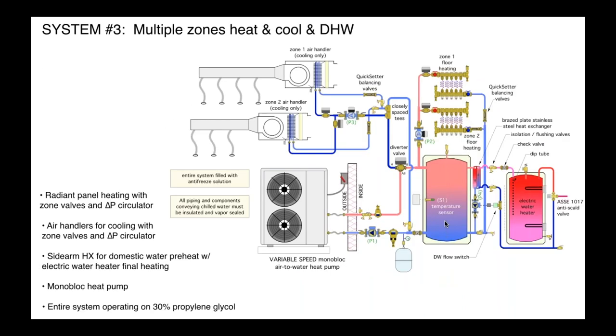And then one more, we wanted to include one here that has zoned cooling as well as zoned heating and domestic hot water. It's a monoblock. It assumes we've got antifreeze in the entire system. In heating mode, we are going through the buffer tank, okay? In cooling mode, though, we're going directly. This diverter valve basically determines, do we go to the hot tank for heating or the chill water side? You'll see there's no buffer tank involved in the cooling side, but I want to stress here that we're not undersizing the coils or these air handlers.